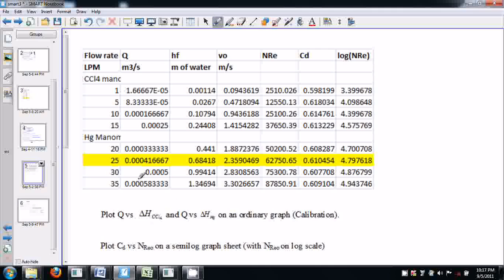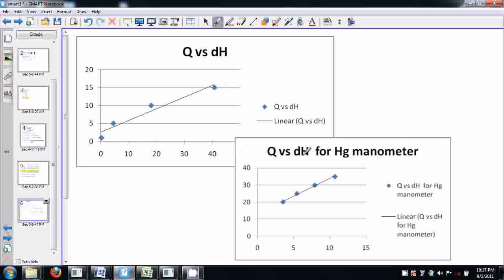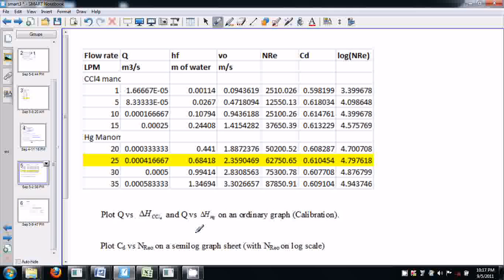Plot a graph of flow rate versus head for the CCl₄ set of readings and the Hg manometer set of readings separately on an ordinary graph sheet. The plots look like this — these are the calibration curves for the orifice meter. Then plot a graph of C_D versus N_Re on a semi-log graph, with log on the x-axis for N_Re. After calculating Reynolds number and coefficient of discharge, one can cross-check the calculations with the simulator-calculated values.